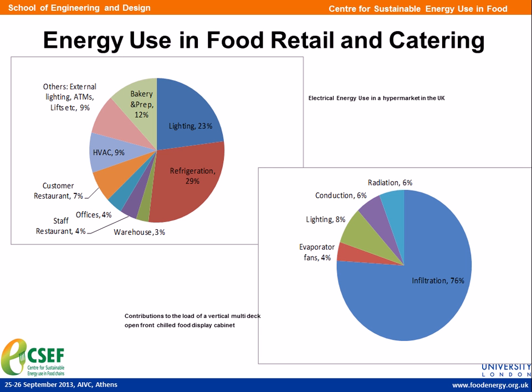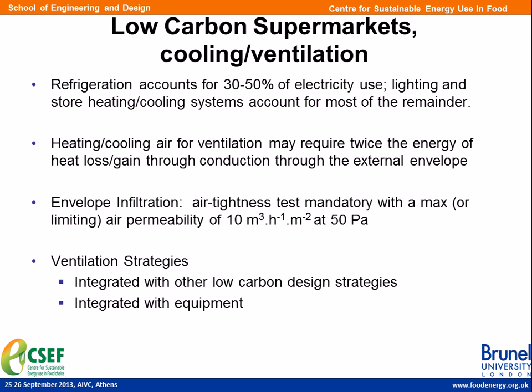Narrowing and focusing more, if we look at supermarkets, the electrical energy used in a typical hypermarket in the UK is high in refrigeration, lighting, but also HVAC equipment. And if we look again at the chilled food cabinets, we can see that there is energy use for lighting, and energy loss through conduction, radiation, and evaporator fans. But infiltration accounts for more than three quarters of the energy use, and quite a lot of research has been carried out to improve this in refrigerated cabinets.